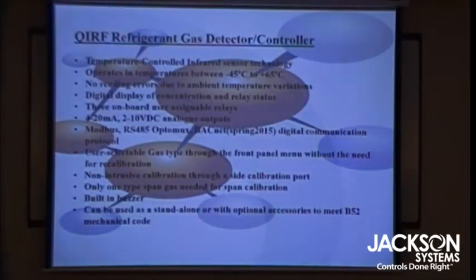The advantage in a refrigeration application, if you're doing chiller maintenance and you're recalibrating sensors, is that you could have customers with a whole gamut of gases. All you need is one test gas. Basically, you go to that area, to that office or that plant, and you switch the gas on that sensor to the gas type that you have, calibrate it, then switch it back, and then go to the next spot. So it really cuts down on the amount of gases that you need and makes it very flexible.